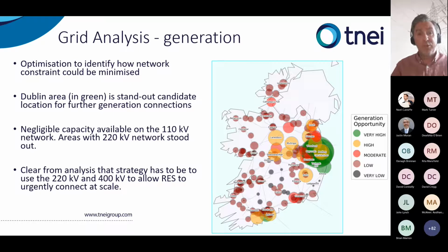The results show that Dublin was a standout, if obvious, location for further generation. It was clear that solar could be well accommodated on the 110 kV network, but that onshore probably could not. It was kind of clear from the analysis that onshore had to utilize more of the 220 kV and 400 kV grid, where there is capacity or potential for additional capacity. This aligns with the urgency required here, to make large scale RES connections where possible, to ensure that by the middle of the decade there are RES-E gains and ultimately carbon reductions as well.